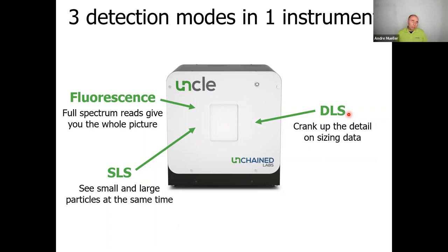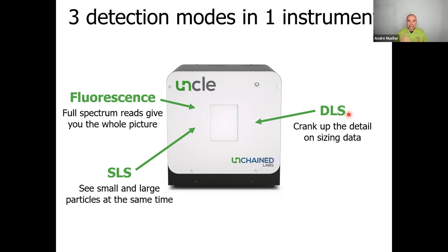The diameter for an AAV would be around 30 nanometers, so if you see something much larger at the beginning, it may be a good idea to re-prep or investigate why aggregation has already occurred. UNCLE also has temperature control — you can set the temperature between 15 and 95 degrees Celsius and ramp or keep it steady, making UNCLE ready for both isothermal and ramping experiments.